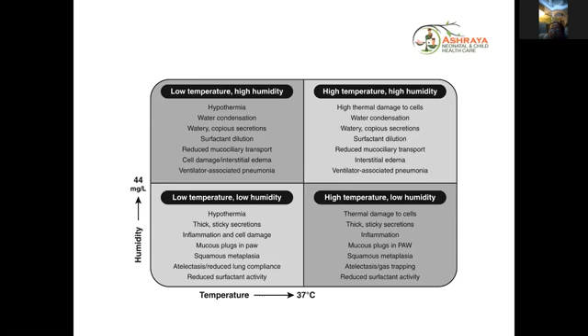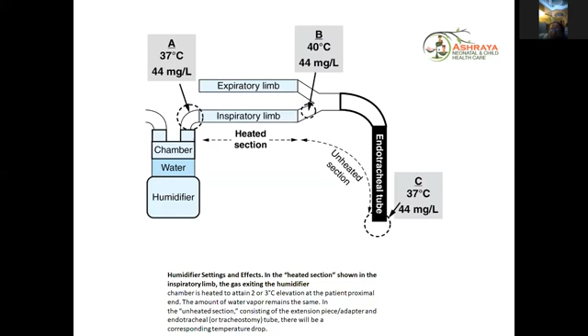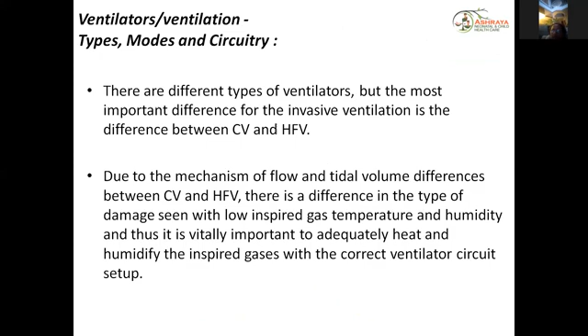So in the heated section, usually you expect that the temperature is almost 3 or 4 degrees more, and in the unheated section, where there is the endotracheal tube and before it reaches the lungs, the temperature again comes down to 37 degrees Celsius. So that's how it works. Initially the temperature is more in the heated section, and in the unheated section it comes down to the temperature which is required. There are different types of ventilator modes, like high frequency ventilation and conventional ventilation, so there are different kinds of damage which can happen with different kinds of ventilation also.